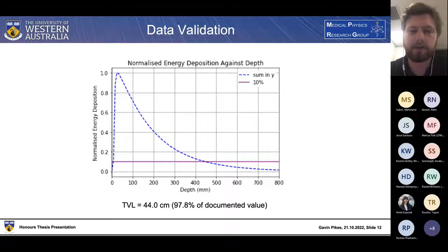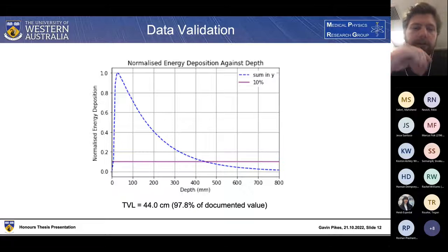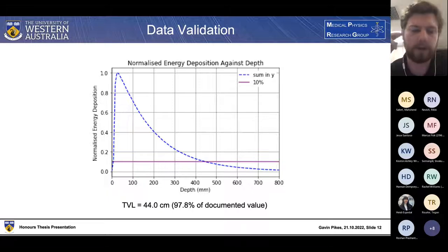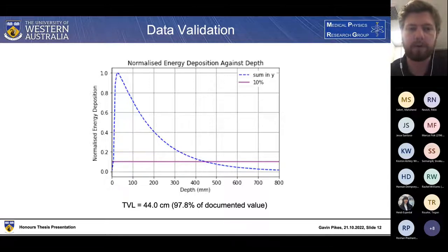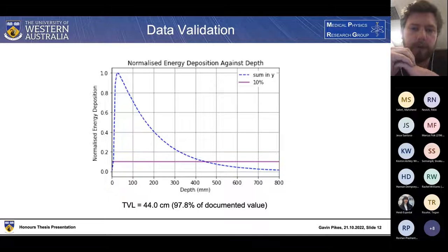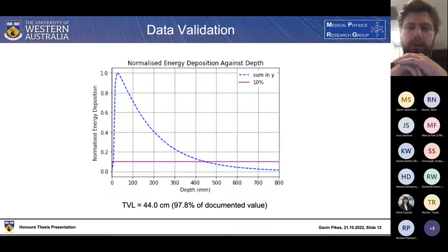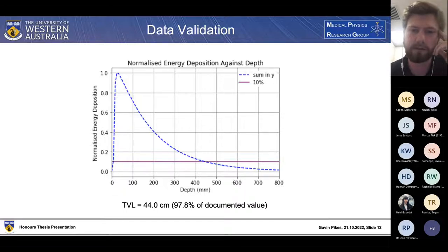Looking at the tenth value layer of the primary barrier: we're plotting energy deposition in the primary barrier as a function of depth, following a photon attenuation curve. The simulated results are in blue, with the 10% energy deposition line in purple. These two lines intersect at 44.0 centimetres, which is 98% of the documented value of the 45-centimetre TVL for an 18 MV beam — again showing a high level of agreement between simulated and measured results.